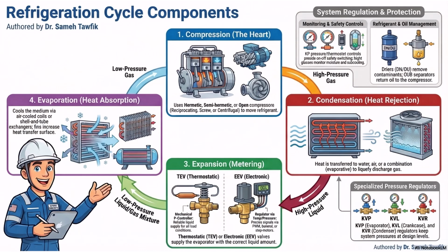That is fascinating. Okay, so we have the core loop mapped out. We do. The compressor pumps the gas, the condenser dumps the heat overboard, the expansion valve strictly meters the pressure drop, and the finned evaporator absorbs the new heat. It's a beautiful, continuous cycle. It really is elegant. But in the real world, things aren't perfectly stable.